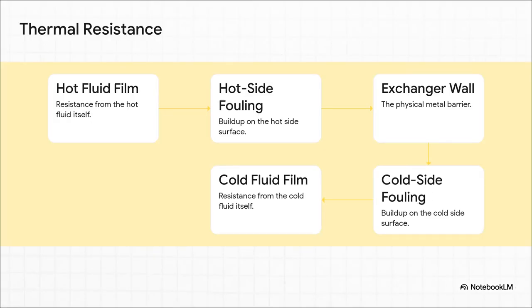And that thermal resistance we just talked about? It's not just one thing, it's more like a 5-part obstacle course. Imagine you're a little packet of heat. First, you have to push through the film of the hot fluid itself. Then you've got to fight through any layer of fouling on the inside wall. Step 3 is crossing the actual metal wall of the exchanger. Then you might navigate another layer of fouling on the cold side before finally passing into the cold fluid film. Every single step is another hurdle.